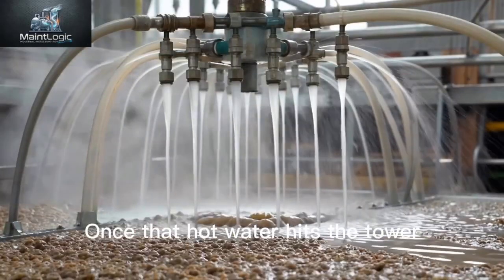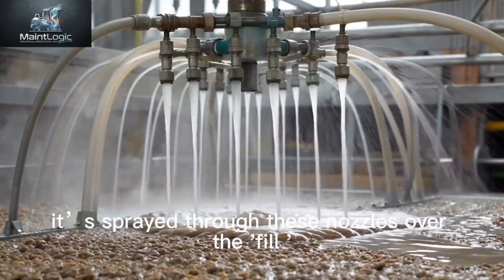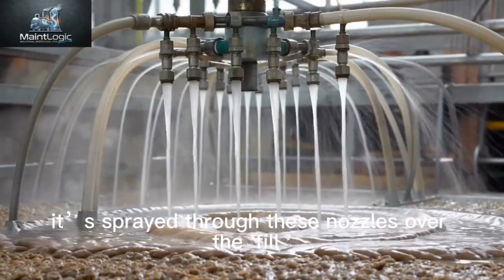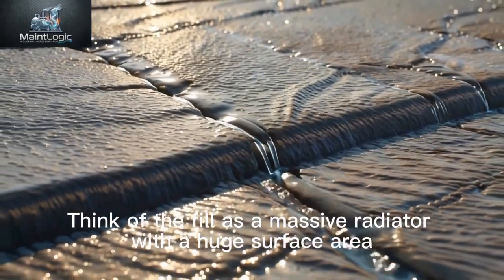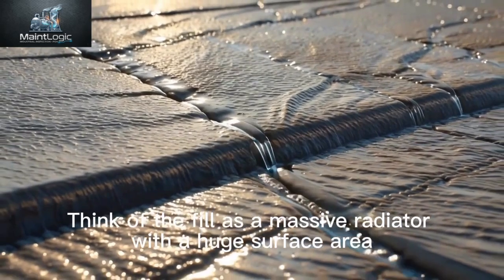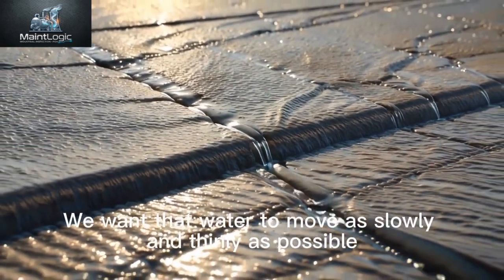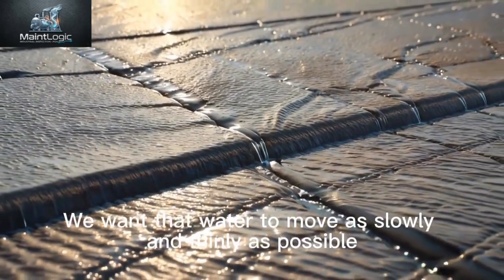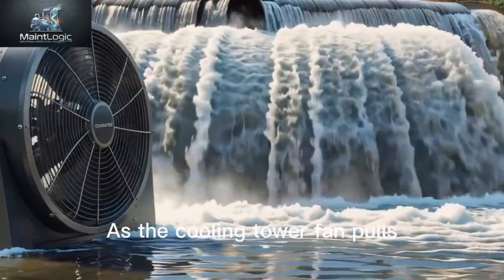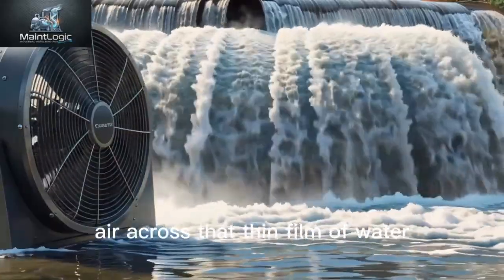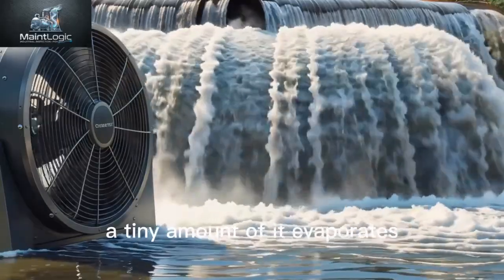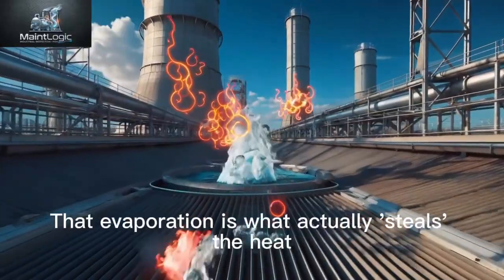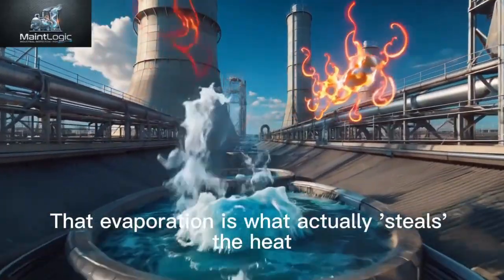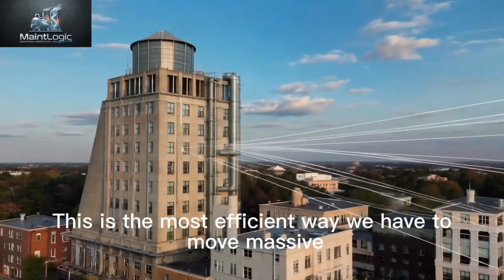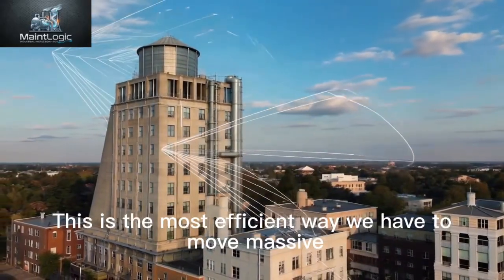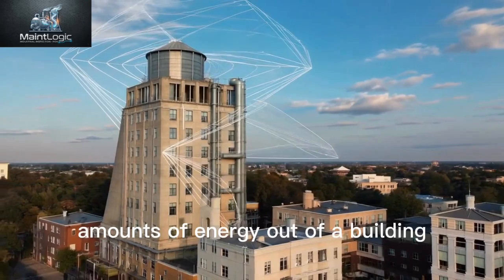Once that hot water hits the tower, it's sprayed through these nozzles over the fill. Think of the fill as a massive radiator with a huge surface area. We want that water to move as slowly and thinly as possible. As the cooling tower fan pulls air across the thin film of water, a tiny amount of it evaporates. That evaporation is what actually steals the heat from the rest of the water. This is the most efficient way we have to move massive amounts of energy out of a building.